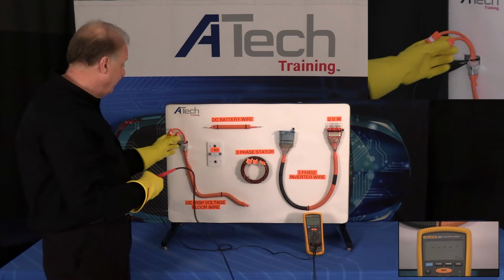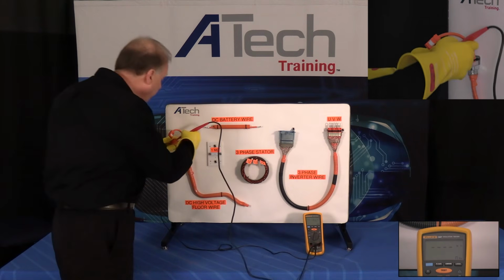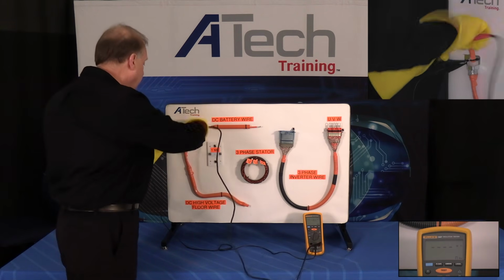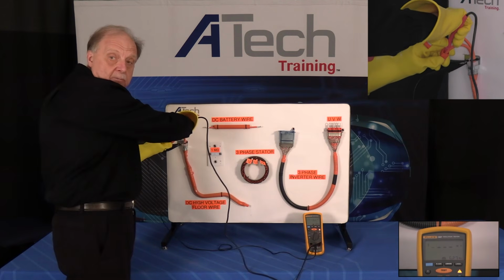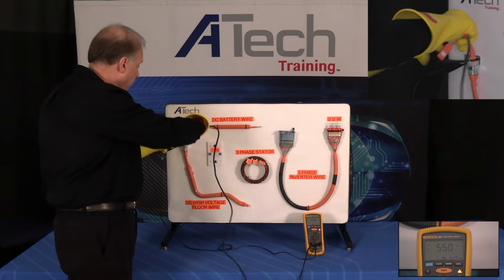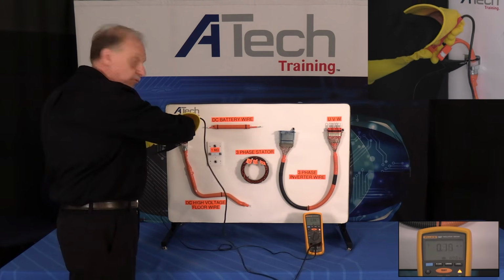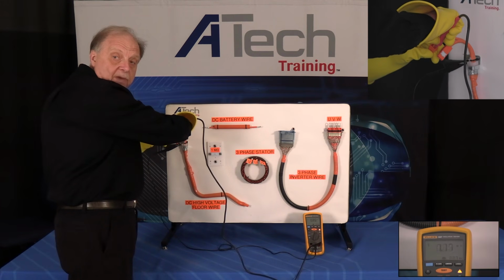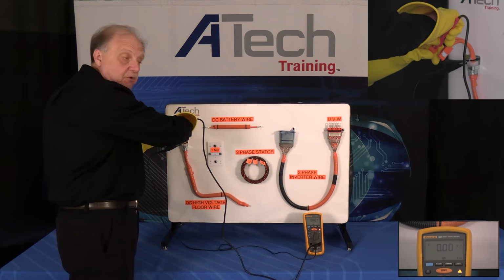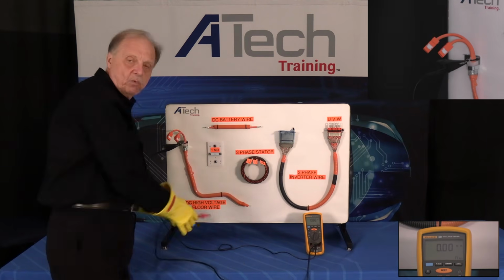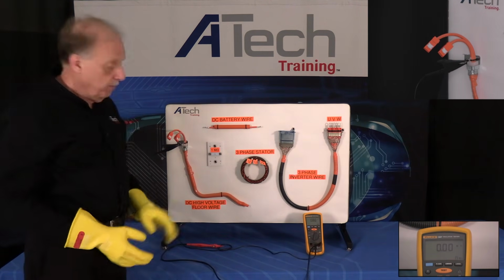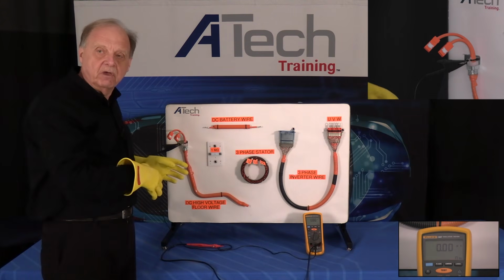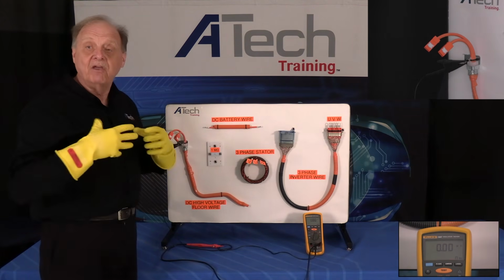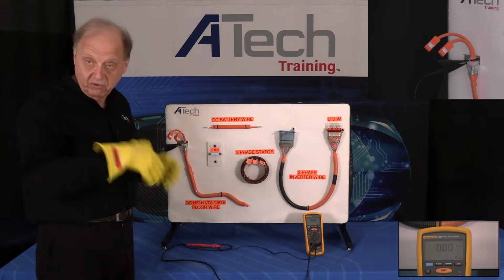Now, we know that one is good, so I want to go over to my second wire. Notice we have two wires up here. I'm going to push over to that one, get a good connection if I can, push a button on that one, and it says 550. Let's go back again. Right now I'm going back to this other wire up here, and notice I have a reading that's not the 550 I'm looking for. So it goes to zero. If I was on a regular meter, that would be continuity. But I'm putting voltage into the circuit, so that means the circuit is shorting to ground.